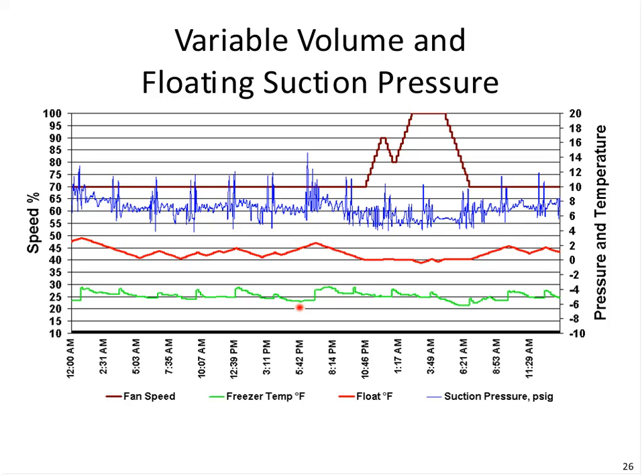Then notice here the temperature in this space goes above the set point, so the float returns to 0, and we're still above the set point, so the fan begins to speed up. This may be at a time when a product or something arrives to the warehouse, and of course there's heat to be removed out of that. So the suction pressure, notice, is lower here. Fan speeds up to the highest speed. We're not getting any float out of it.